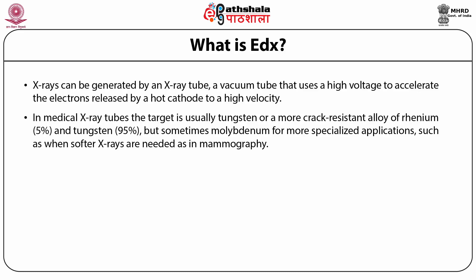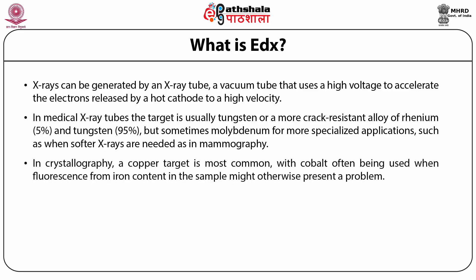Sometimes molybdenum is used for more specialized applications, such as when softer x-rays are needed, as in mammography. In crystallography, a copper target is most common, with cobalt often being used when fluorescence from iron content in the sample might otherwise present a problem.